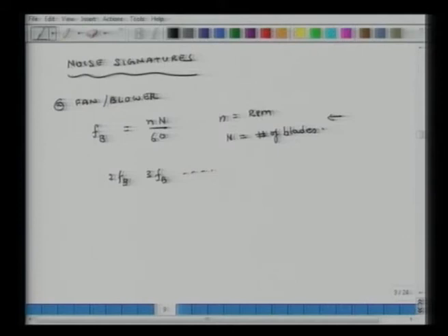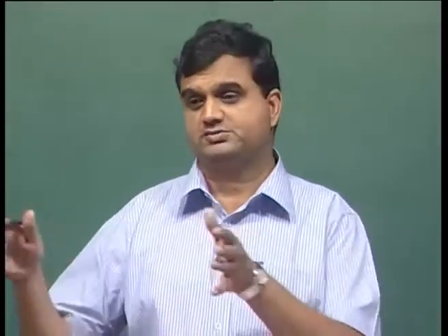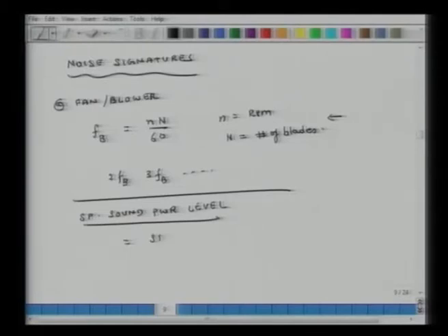In case of a fan, because these generate a lot of noise, once we have figured out LW, at this point we also introduce another term called specific sound power level. This particular parameter helps me compare noise characteristics of one fan with respect to another fan in a normalized way.